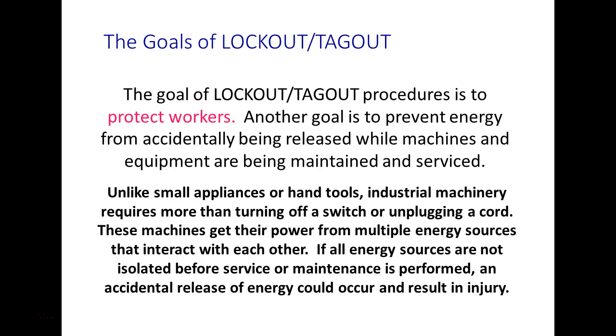Pneumatics or hydraulics. What is the problem with pneumatics? Even if I lock and tag out the compressor, what's the problem with it? Yeah, it has stored energy. So even inside your piping, if you lock and tag out your system, the piping is going to store energy.